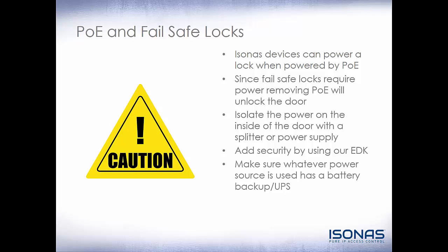Let's take a minute to talk about PoE and failsafe locks. Isonas devices can power a lock when powered by PoE. Since failsafe locks require power, removing PoE will unlock the door. The best way to resolve this is to isolate the power on the inside of the door with a PoE or PoE Plus splitter or a power supply, then add the additional security by using the Isonas Exterior Door Kit or EDK. Make sure whatever power source you're using has a battery backup or UPS.